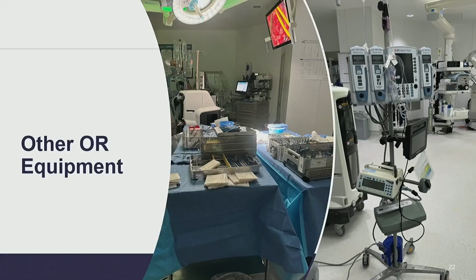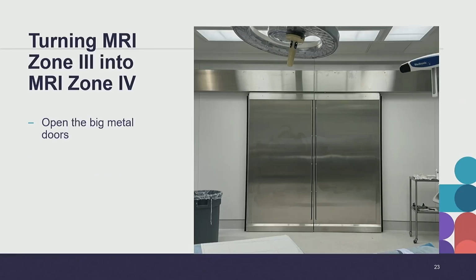We have other OR equipment. This is our MRI OR, and you can see, we're just using regular trays, and these are all metallic. So all of this has got to be cleared out far enough away so that when these big doors open to the scan room, nothing is going to get pulled into the scanner.